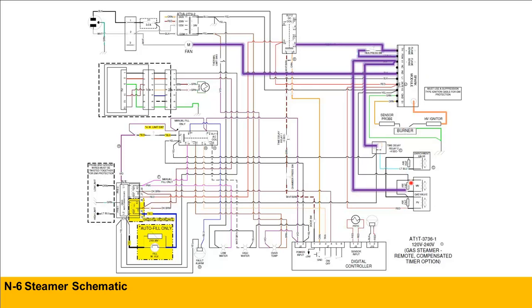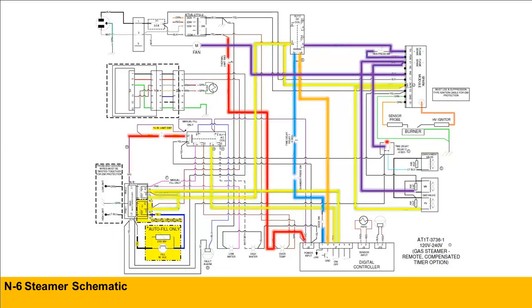All right, so basically what we looked at, in this case, obviously, we tested everything and everything looked good. This pretty much covers I'd say 98% of the issues we see in the field, and we still got that little 2% of things that don't make sense. And when we come across that 2%, when we tested everything, and based on what we're seeing, everything should work, and you see everything comes together: we have our safety, we have our AC voltage, then we have our DC circuit, and then we have our ignition circuit.